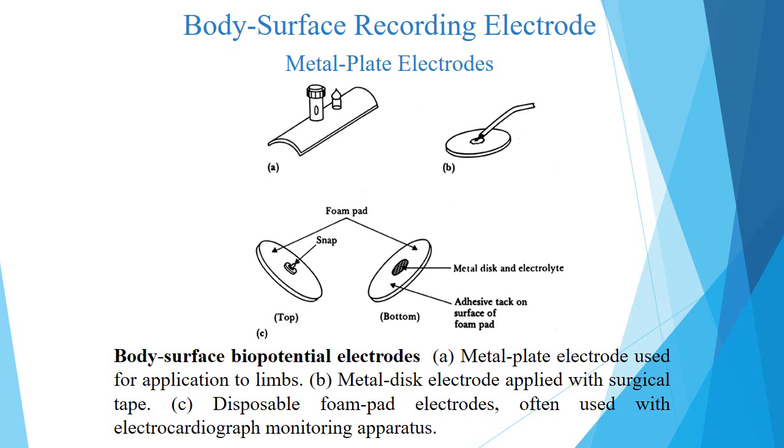Then the next type is the adhesive type. What is the adhesive? It is a gum-like tape electrode. The pressure of the surface electrode against the skin may squeeze the electrode paste out. To avoid this problem, the adhesive tape electrode is used. It consists of a lightweight metallic screen backed by a pad for electrode paste. And this is shown in the figure over here.